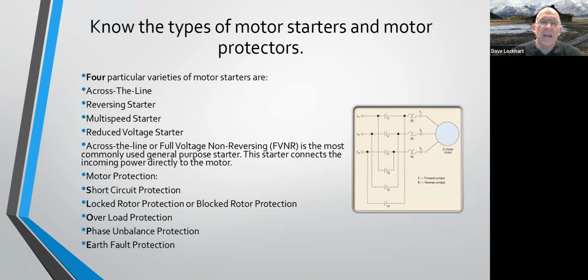And you can identify if you've got a short circuit. Locked rotor, if the load is on or something that should start the motor with less of a load, that high amperage will help trip it, not cause the motor to fail. Overload protection is pretty straightforward. Kind of goes with that locked rotor. Phase unbalance. Let's say you're not providing all 3 phases to that motor, you're going to have problems and will probably burn out that motor. So if you don't have all 3 phases, that's another protection. And then, of course, the earth ground fault protection.